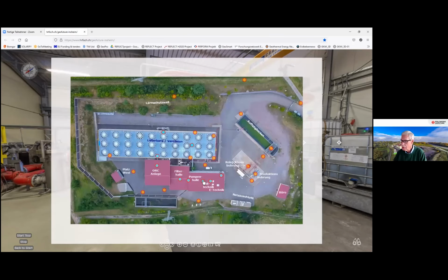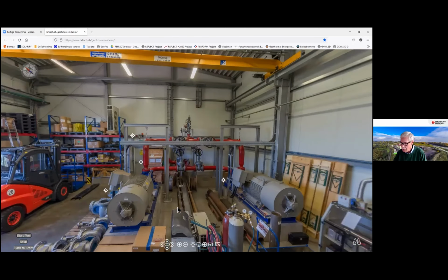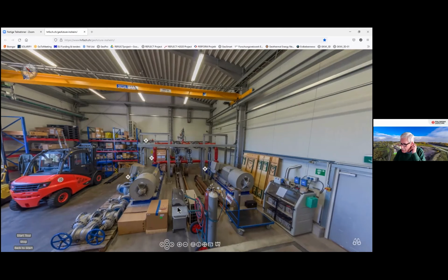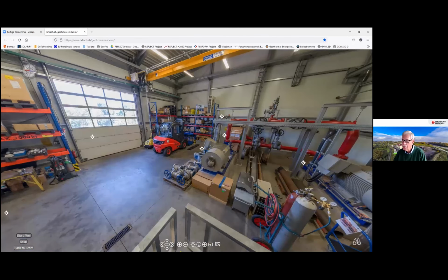So from here, we'll take a short look in our storage hall. When our power plant was designed, the designers had learnings from the Landau power plant, which suffers from very low permeability on the reinjection side - they can only reinject the brine using a reinjection pump. So the designers thought it might be necessary on our side as well, and right from the beginning, 2 large reinjection pumps were planned and installed. But they have never been used, thanks to the later drilled sidetrack in our reinjection well. Therefore we have a very low reinjection wellhead pressure, thanks to excellent permeability on the reinjection side. These very power-consuming reinjection pumps have fortunately not been needed so far, and I hope this will not change.